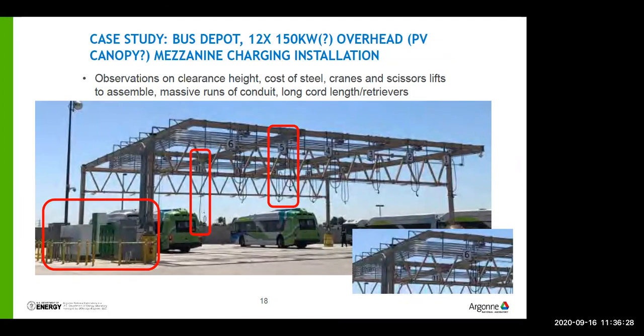The red rectangles on this canopy show: that's a lot of steel, that's even more conduit, and that's a lot of cords dangling from the ceiling going up and down. The skinny rectangle in the center shows one extended, with a curlicue shape—that's the winch that lets the cable down to plug into the bus. The rectangle to the right shows what these 12 cables look like pulled up, hundreds of feet of cable. In the lower left you can see, for the utility-savvy, lots of skinny bollards protecting the panel boards, the low voltage transformer, and the green cabinets in the middle—those are the power electronics converting 480 volt three phase AC to roughly 500-600 volt DC at 400 amps.